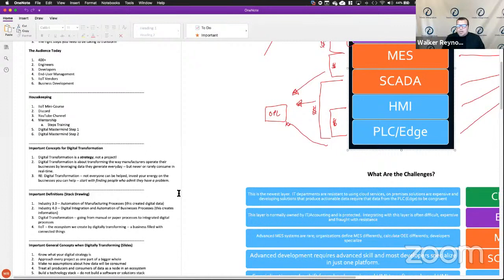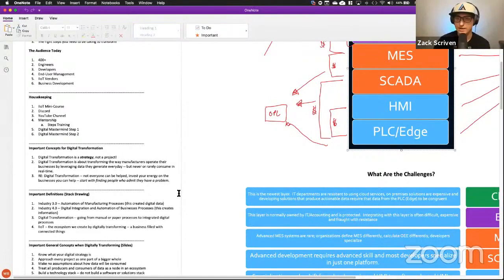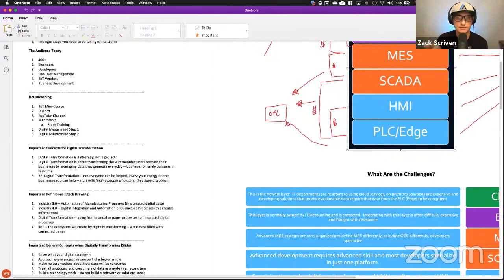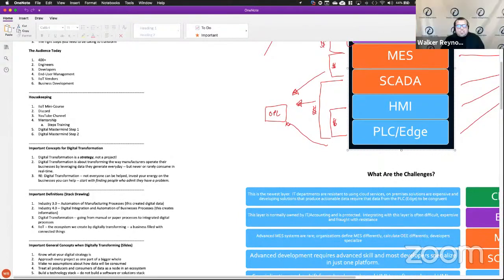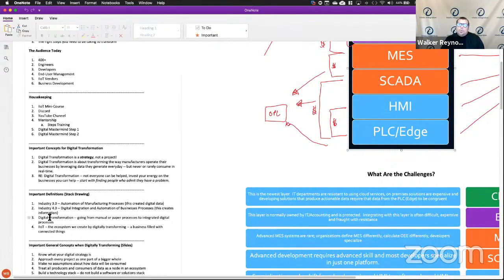Can OSI Pi serve as a unified namespace? The answer is yes — people have asked me this several times and it absolutely can. So can Canary Labs. But that doesn't mean you should use it as your unified namespace. The same pharmaceutical company proposed using OSI Pi as their unified namespace and asked if they could. I said you can, but you shouldn't. You can still use OSI Pi to build asset frames and be a single source of truth for all time series data, but what you should do is have it publish its entire namespace to a standalone broker, and then have other applications like ThingWorx consume from the unified namespace rather than directly from OSI Pi.